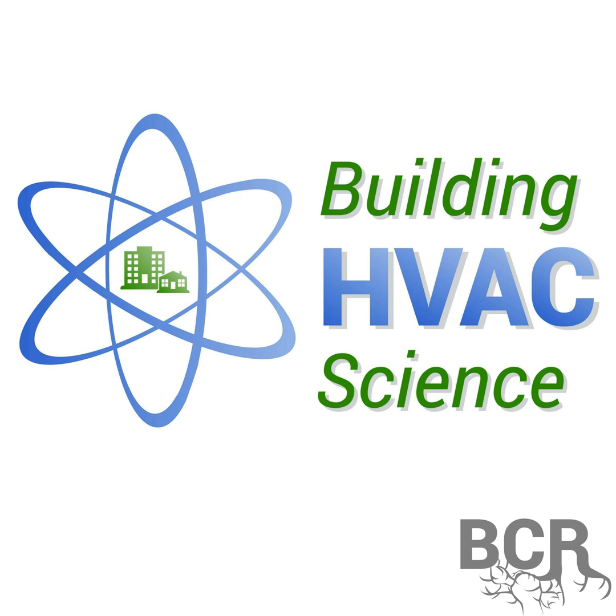The reason for a higher ventilation rate is twofold. First, the basic airflow that we need to stay healthy and to feel good, we feel it should go back to where it used to be several decades ago, which is in the range of about 40 CFM per person, where the typical rule of thumb has been about 20. And then the other reason is that as carbon dioxide is increasing in the out of doors, that's elevating the airflow rates we need, relative to the level of CO2 in the outside, to keep the indoors at a reasonable level of CO2 concentration.